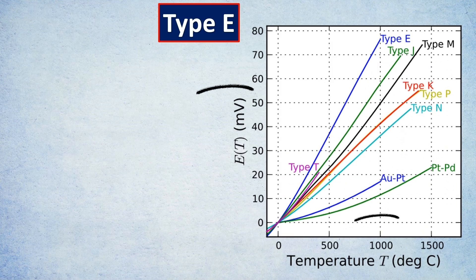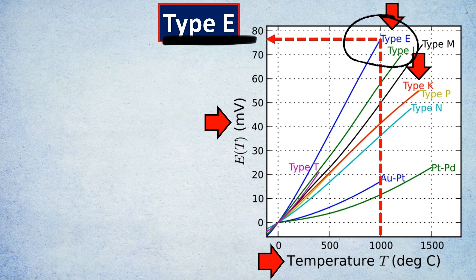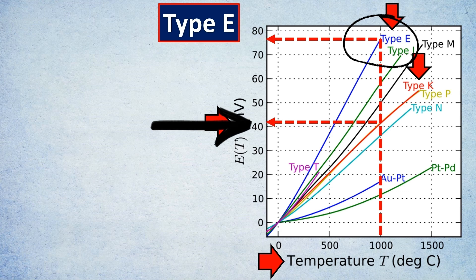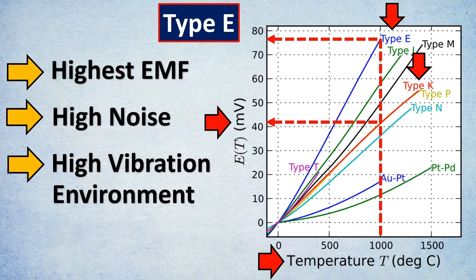Type E thermocouples: if you see the EMF chart versus temperature, you'll notice Type E generates the highest EMF at around 78-79 millivolts, compared to Type K at just 42 millivolts. In cases where you require the highest EMF—in high noise requirements or high vibration environments—Type E is the most preferred.